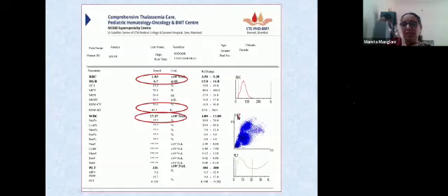But look at the scattergram, it is weird. It has given only blue color. In all our other CBCs, we had different colors. So when you have nucleated RBCs, it gives you a patch like this. It does not help the counter.